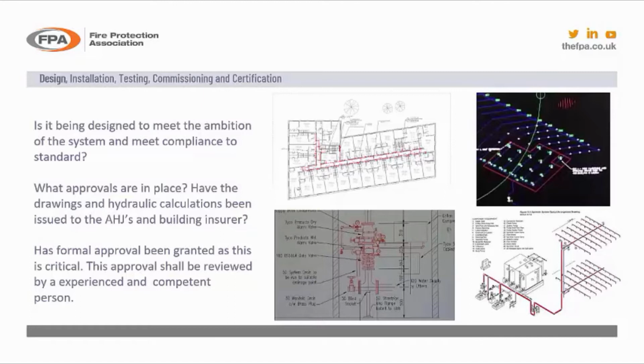So, on the design side, does the design reflect the ambition of the system and what it's desired to do? Is it in compliance with the relevant standard? On completion of the design, have all the drawings and calculations been submitted for approval? And I'm not talking about coordination or approval from, say, the architect who likes the location of the sprinkler and the pipes, and the M&E consultant that says, yes, you're not hitting our pipe work. We're talking about the review of the design drawings and hydraulic calculations by a competent, experienced person from the authorities having jurisdiction, and most importantly, the building insurer. And these drawings and calculations would, if they were submitted, get signed off for final review and inspection.